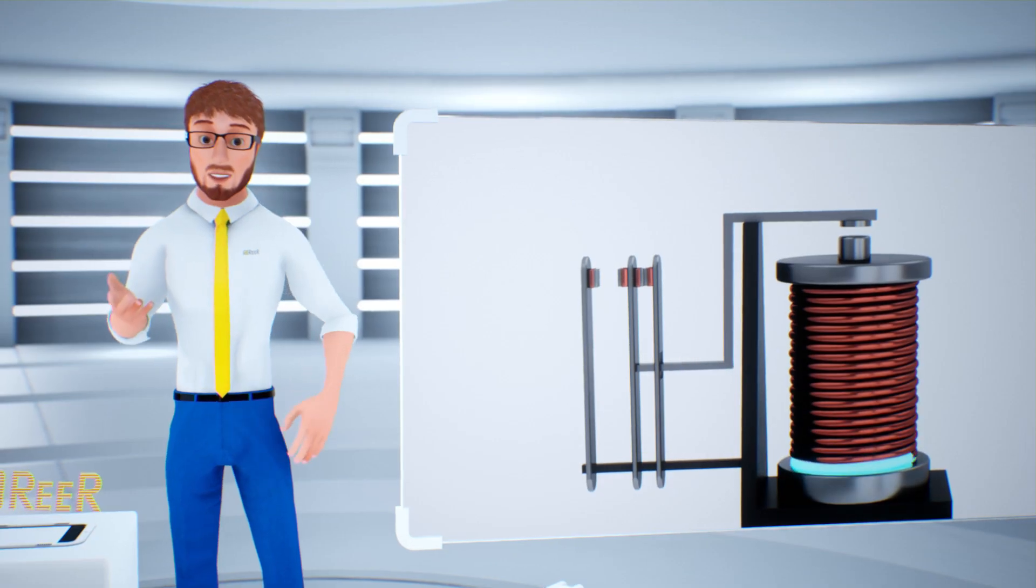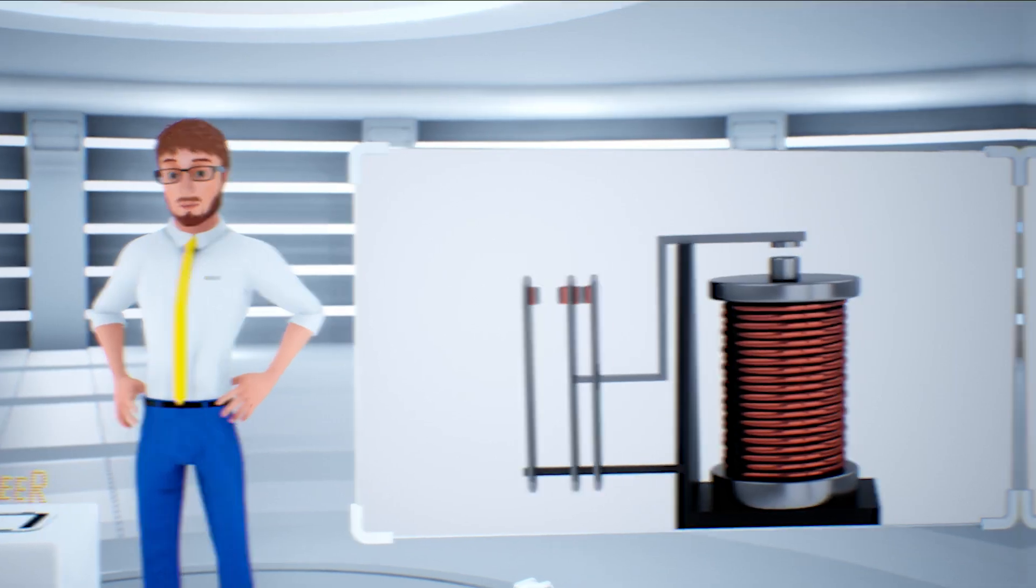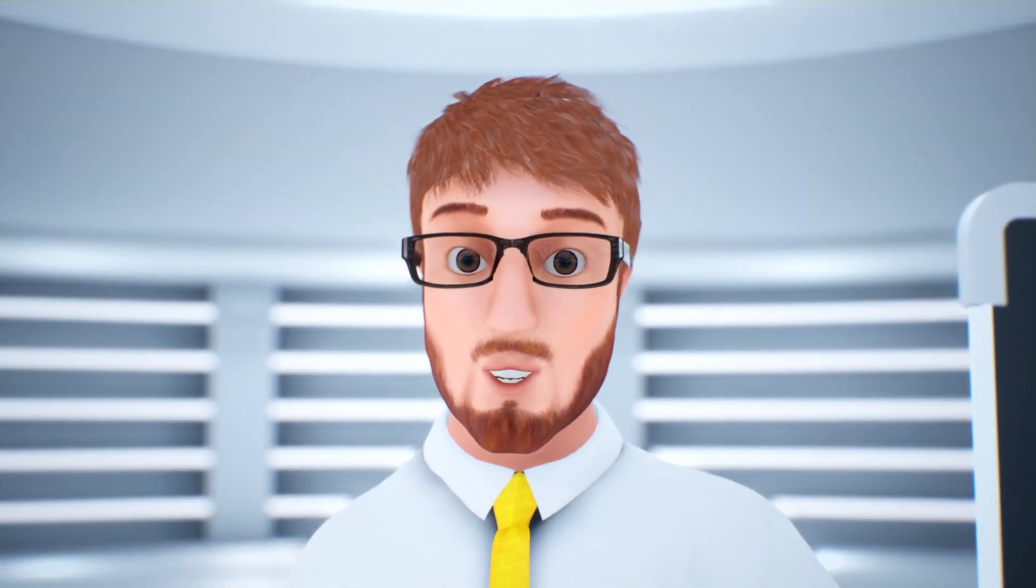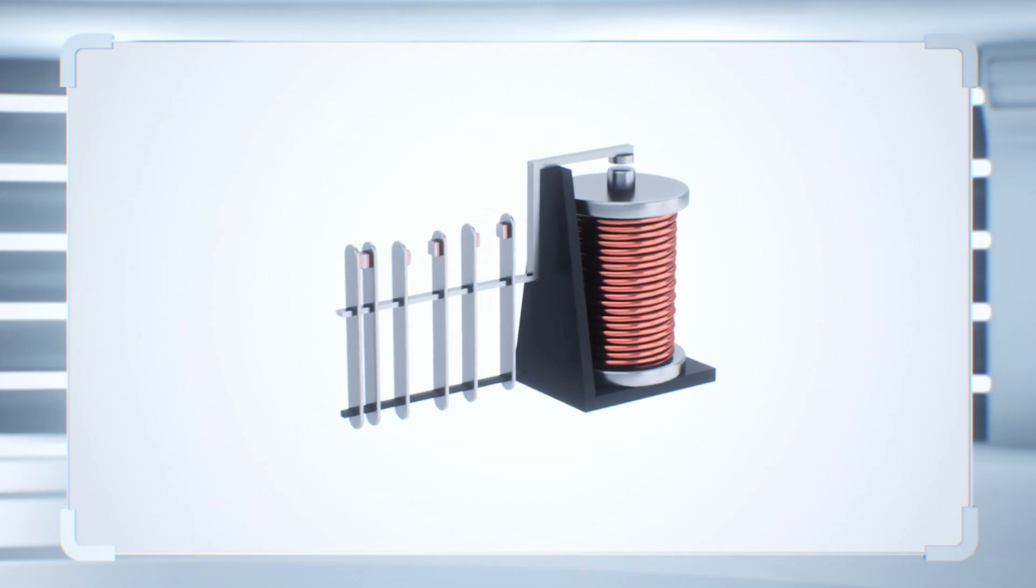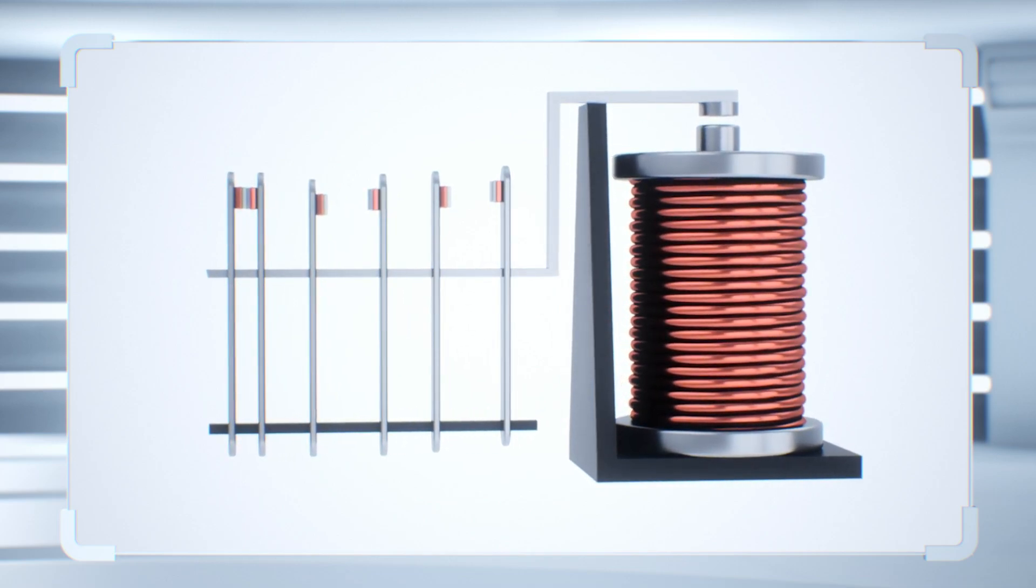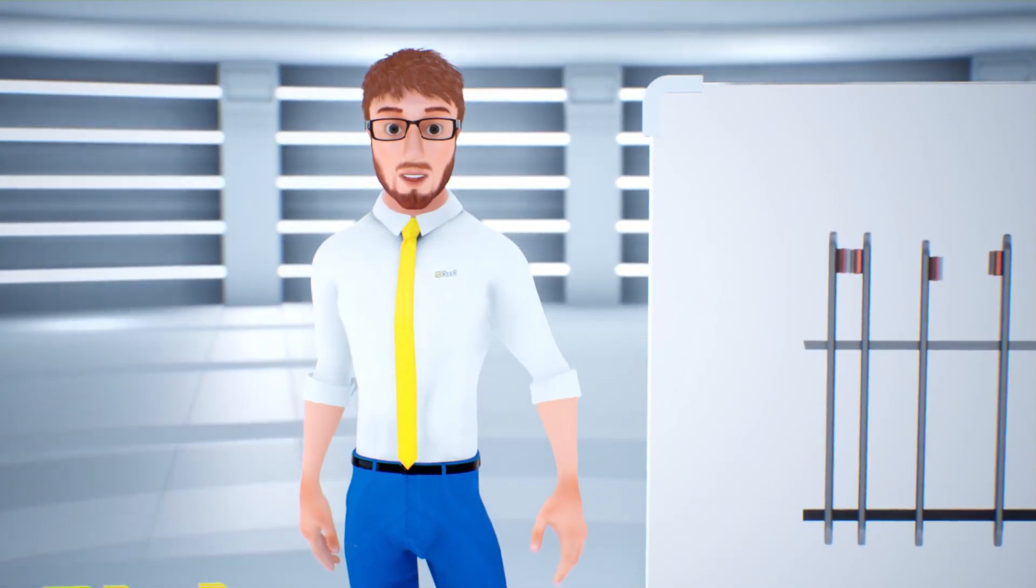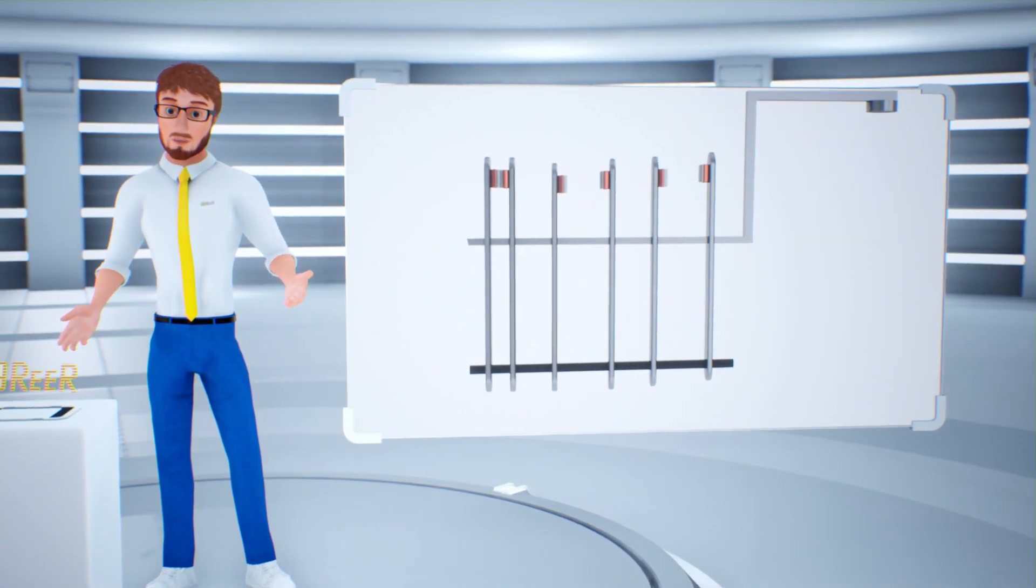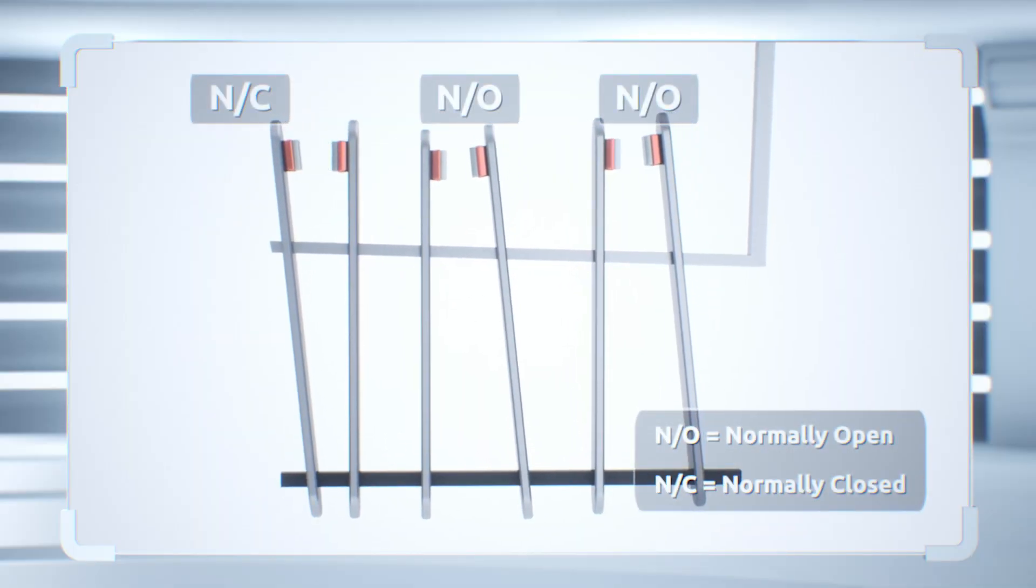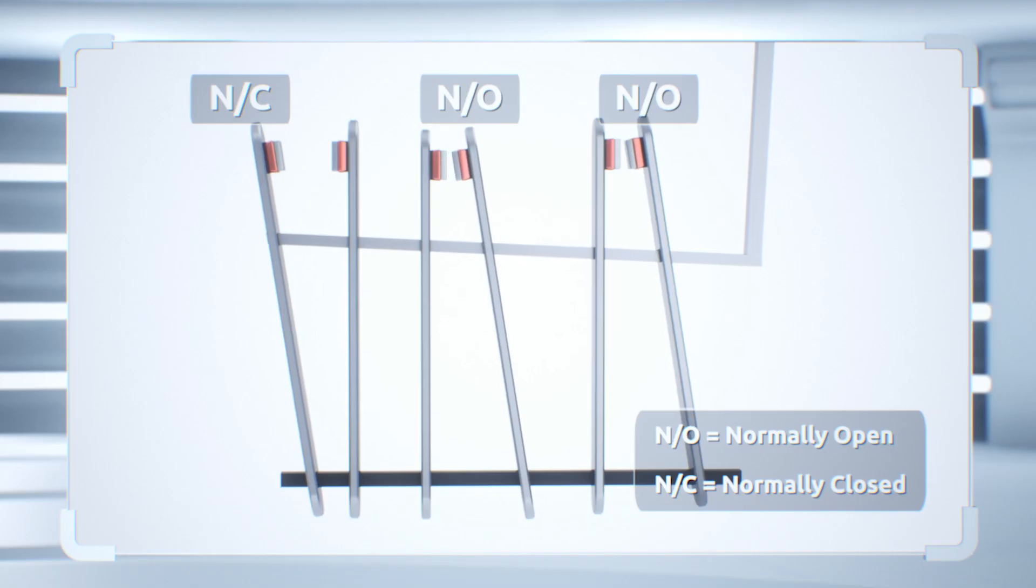The opening and closing of the contacts is called commutation. When we talk about safety, a subject we like a lot, we talk about relays with forcibly guided contacts, or safety relays. This is because there are multiple contacts mechanically connected to each other, typically with contacts open at rest, normally open, used for safety related functions, like stopping and starting a machine, and contacts closed at rest, normally closed, generally used for status and feedback functions.